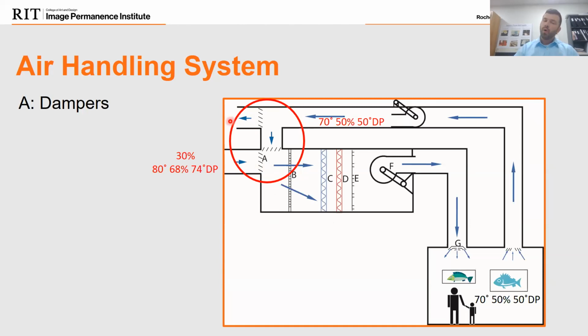So we're going to exhaust about 25 to 30% of that air. And the reason I say 25 to 30% is we'll lose a little bit in the room. Our goal is to make the room positively pressurized. When we talk positive, that means our supply is going to have a little bit more air than the return. So this way we're blowing the room up, if you will, like a balloon. We're going to be pushing that supply air to blow the room up, and on the return, we're going to return a little bit less. So we'll exhaust about 25, 30% of the air. We're going to be returning about 70% of that air, I'm sorry, 30%, no, 70%. And we're going to be bringing in about 30% outside air. So we're going to be mixing this return air condition with this.